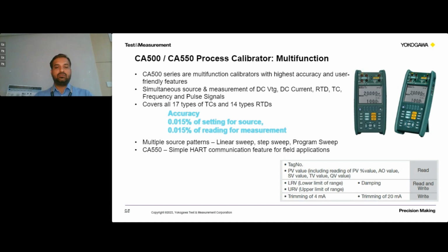And we'll also be able to do the trimming of the 4 milliamps, trimming of the 20 milliamps, and zero trimming is also possible using this CA550. This is the most suitable calibrator for field applications and field HART applications, as we'll be carrying out these activities day in and day out in any of the process industry.